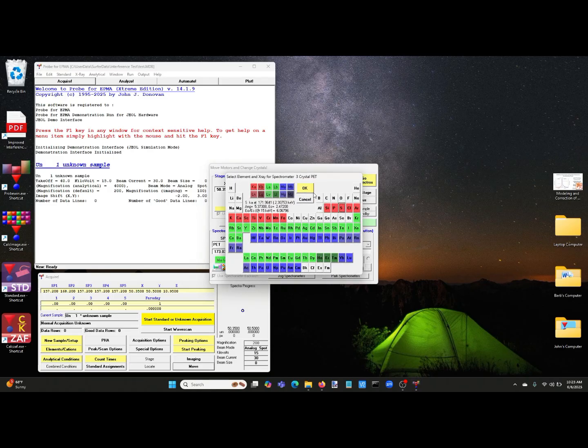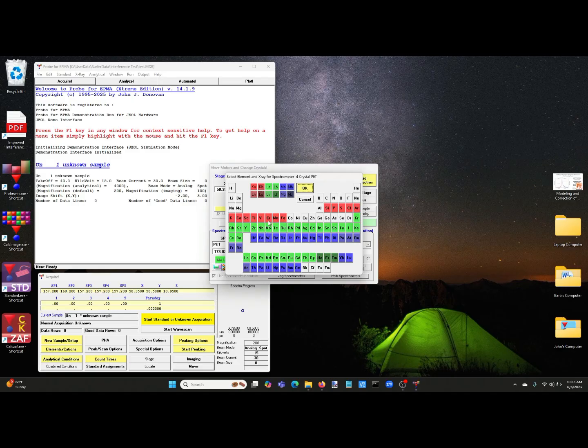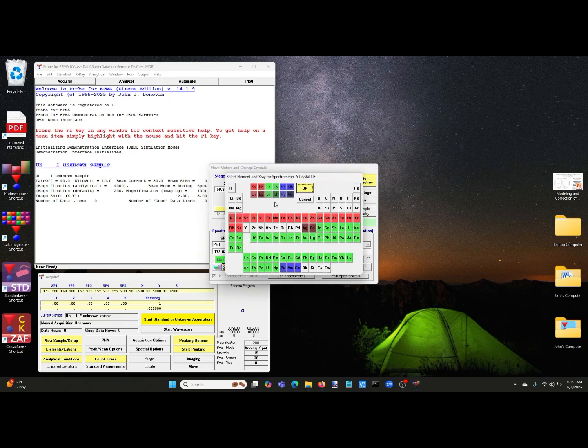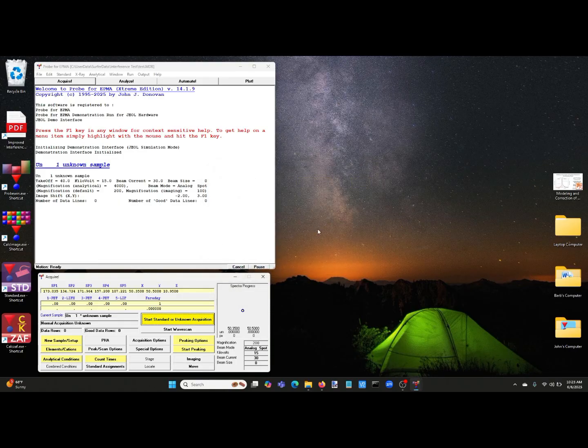The reason for the sulfur measurement is because we need to analyze for not only the interfered element, but also the interfering element. And if we wanted to, say, do iron copper sulfides, we'd also add copper to that. So let's do that on the LIF crystal. And we move the spectrometer to those positions. You can see here. And when it's done, we close this.